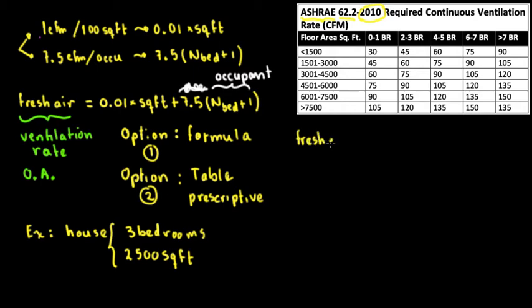Fresh air, or outside air, equals to 0.01 times 2,500 square feet plus 7.5 times number of bedrooms, which is 3, plus 1. So if we do the math, the fresh air CFM is going to be equal to 55 CFM. This is more precise.